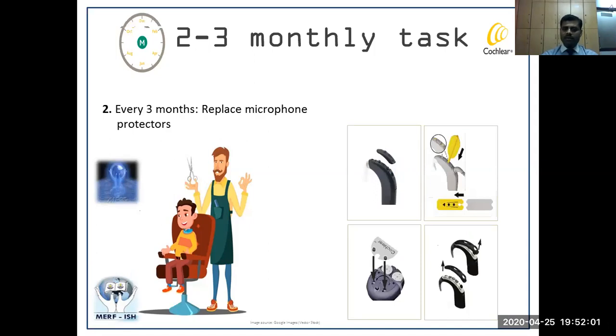Every 3 months, you have to change the microphone protecting cover. Some processors have this cover, some don't. For those that do, it should be changed once every 3 months. Sometimes you may need to change it sooner, especially if the child says they're not able to hear properly. There could be many reasons for this - one could be poor mic sensitivity, but even if the mic itself isn't desensitized, if the protective cover is covered with dust, the microphone sensitivity can be affected. So it's advised to change the microphone cover protector once every 3 months.